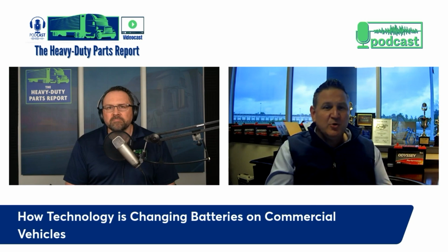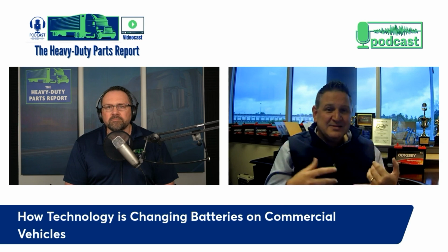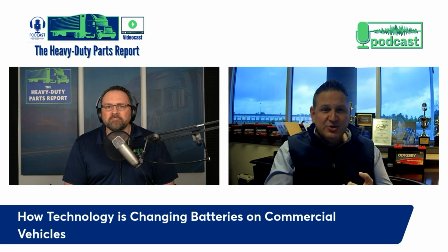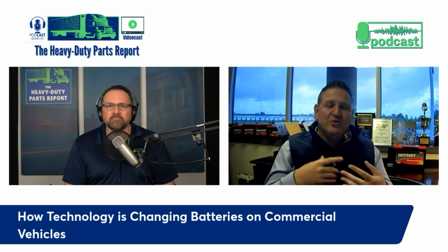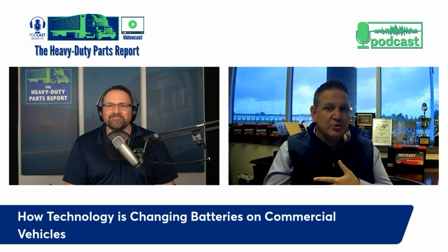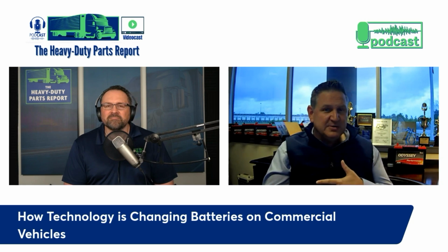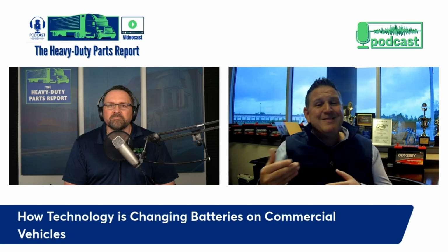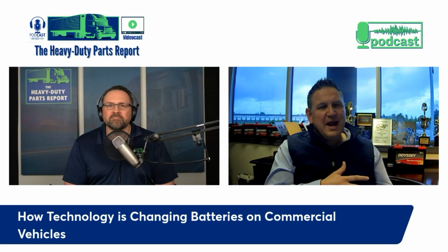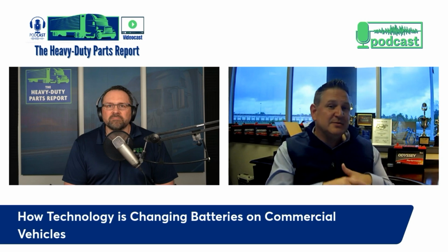You can have different failure modes from dry out, meaning you used up all the water in the battery and gassed it off. You can get sulfation, you can get stratification, you can get all these different things that cause the battery to fail or go dead, so to speak. And that can tell you what in the application it wasn't designed to meet.